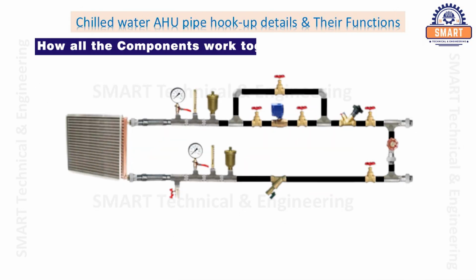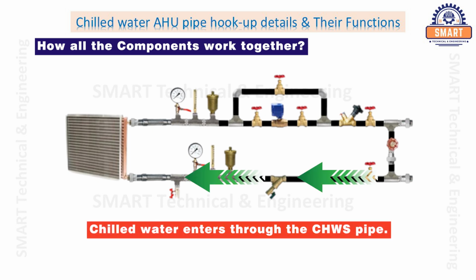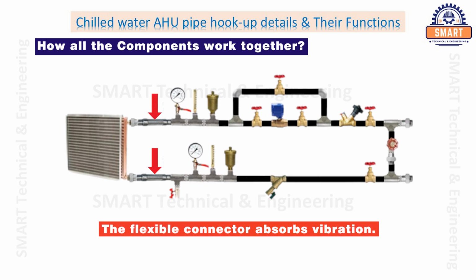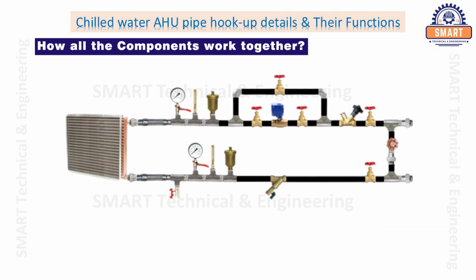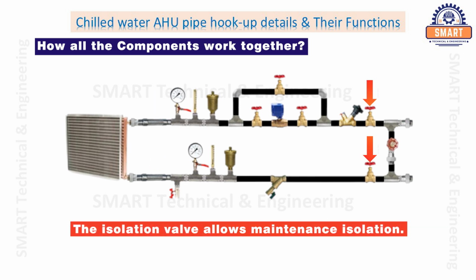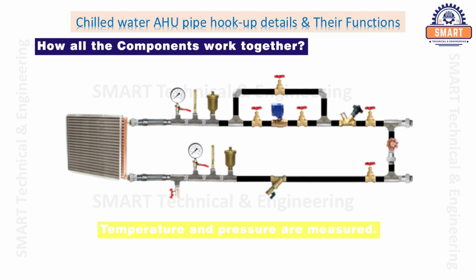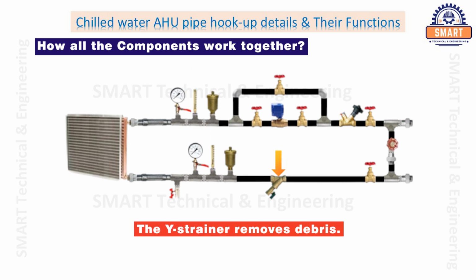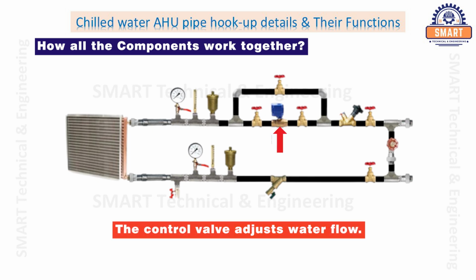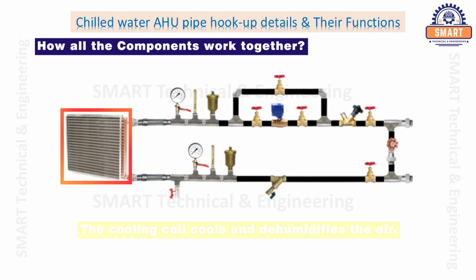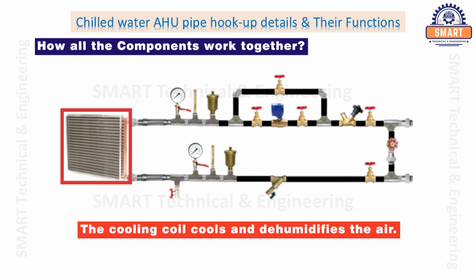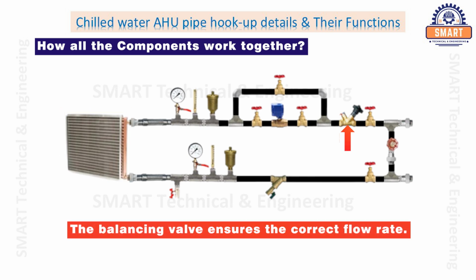How all the components work together. Let's summarize the operation. Chilled water enters through the chilled water supply pipe. The flexible connector absorbs vibration. The isolation valve allows maintenance isolation. Temperature and pressure are measured. The Y strainer removes debris. The control valve adjusts water flow. The cooling coil cools and dehumidifies the air. The balancing valve ensures the correct flow rate.